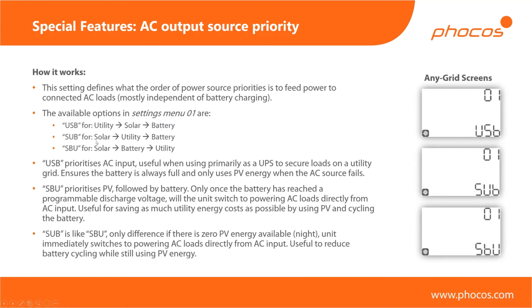The second priority option is solar, utility, and battery. This one will prioritize PV as your first priority. So whatever energy you're producing from your solar modules, your solar panels, you'll be able to use that directly for your loads and obviously charge your battery at the same time. As a second priority, you're using utility. In this case, we don't have a hard switchover between the grid and the off-grid scenario. Instead, let's say you're producing 1 kilowatt from your PV, and you need 2 kilowatts for your loads. Then 1 kilowatt will come from solar, and the remaining kilowatt will be mixed in from the grid at the same time. So there's no hard switching in this scenario.